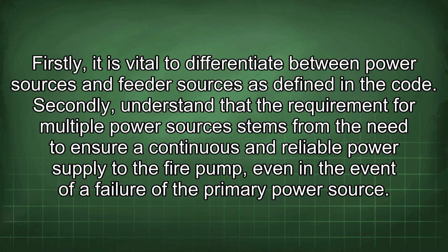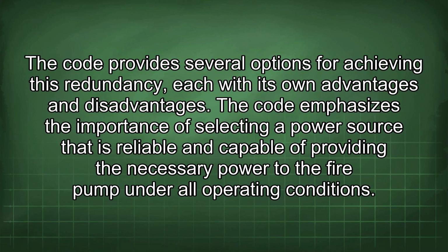Secondly, understand that the requirement for multiple power sources stems from the need to ensure a continuous and reliable power supply to the fire pump, even in the event of a failure of the primary power source. The code provides several options for achieving this redundancy, each with its own advantages and disadvantages. The code emphasizes the importance of selecting a power source that is reliable and capable of providing the necessary power to the fire pump under all operating conditions.